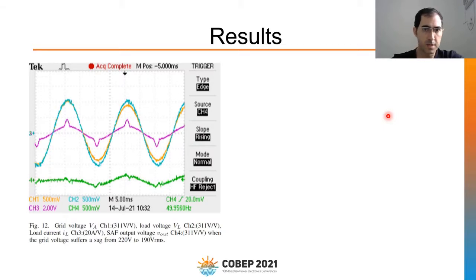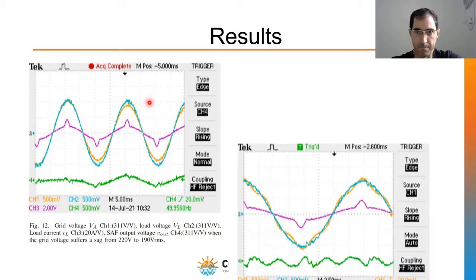Another result is when we have a sag from 220 volts to 190 volts. Initially, there is no sag, so the distribution system voltage is already sinusoidal. The series active filter does nothing. At this point, the voltage at the distribution system suffers the sag, but we can see that the load still keeps receiving the amplitude that is desired for such a system.